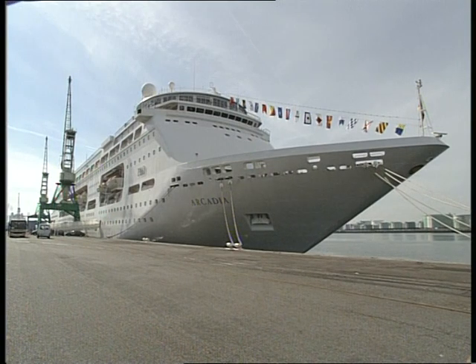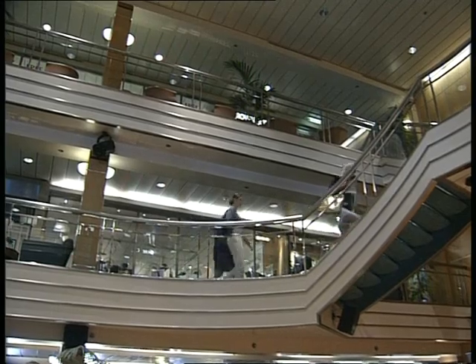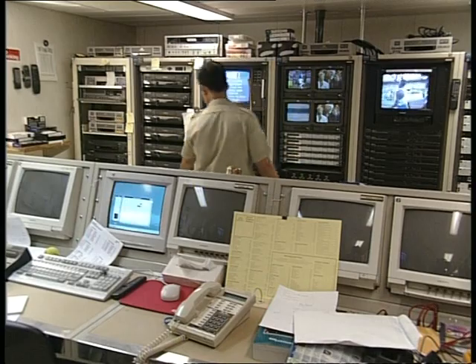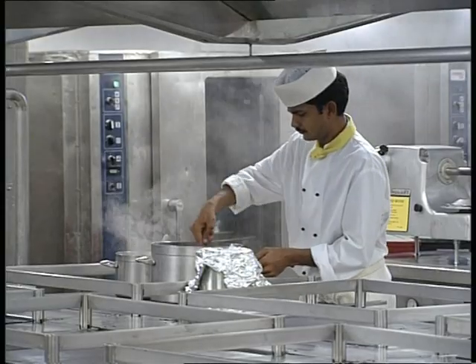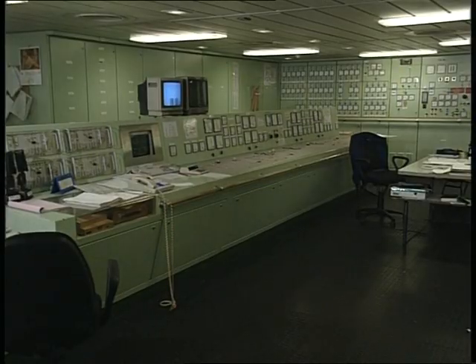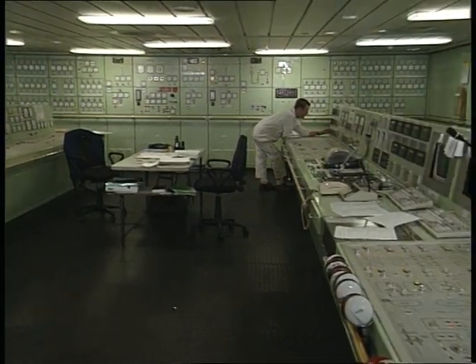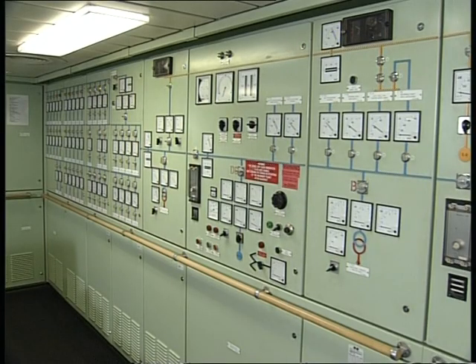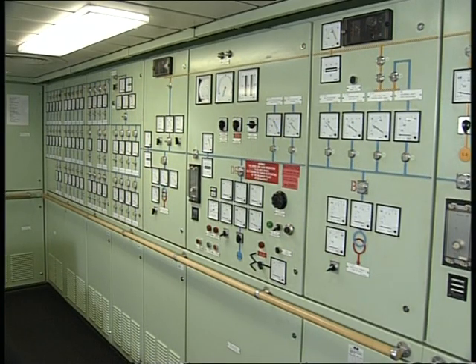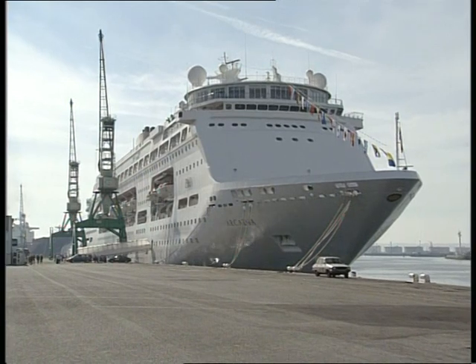In addition to propulsion, especially in the cruise liner sector of the market, there are many other services which utilize the generated electric power. Power is needed for the hotel areas, for passenger comfort, for entertainment, for the lifts, the galley, the air conditioning plant and telecommunications. A ship with such comprehensive requirements in effect houses a central power station which must be able to meet the varying demands whilst maintaining the supply voltage and frequency constant. So in contrast to the average ship requirement of one to three megawatts, a modern cruise liner supporting comprehensive hotel facilities might require more than 40 megawatts.